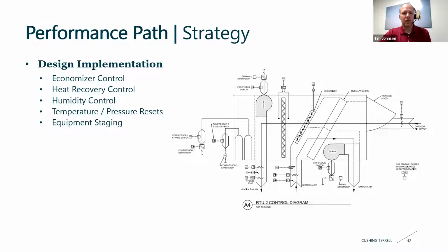Let's take a look at the HVAC systems. How are they operating? Can we tweak the economizer controls? Should we control based on enthalpy or dry bulb temperature, for example? How about heat recovery? Are there times we need to turn off the wheel so we can economize, or bypass it altogether? We can look at temperature and pressure resets.